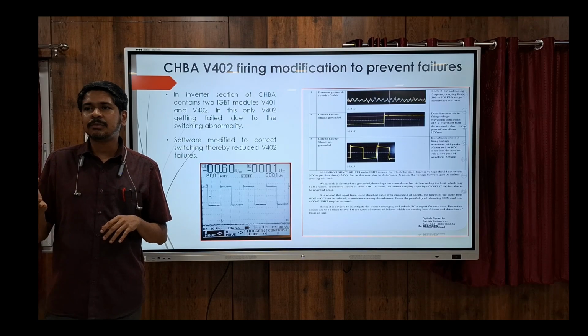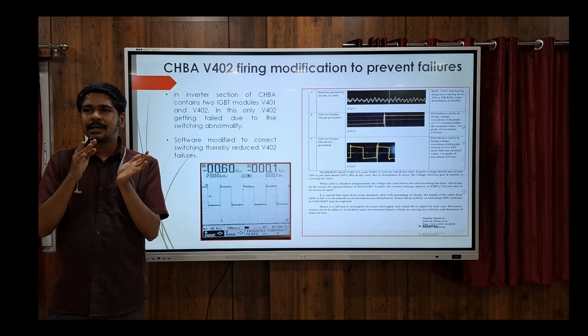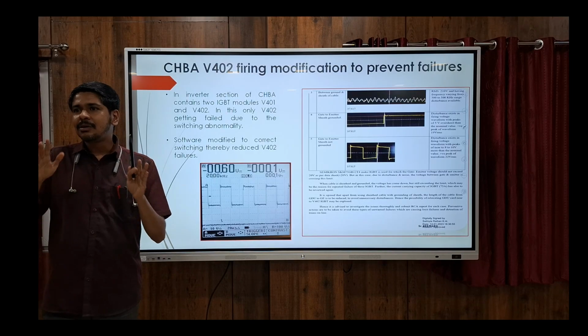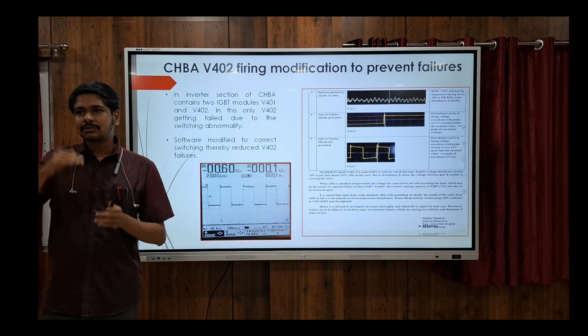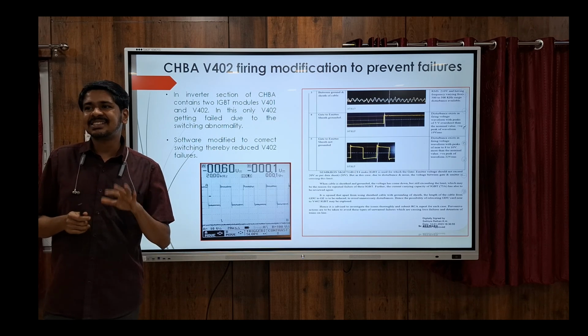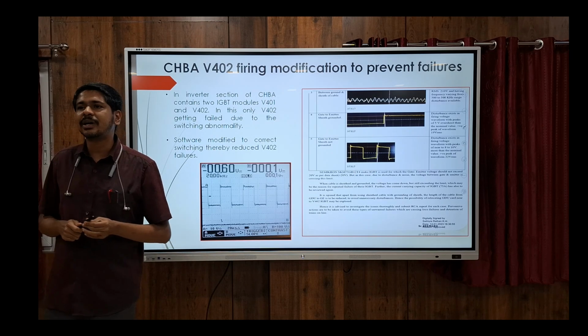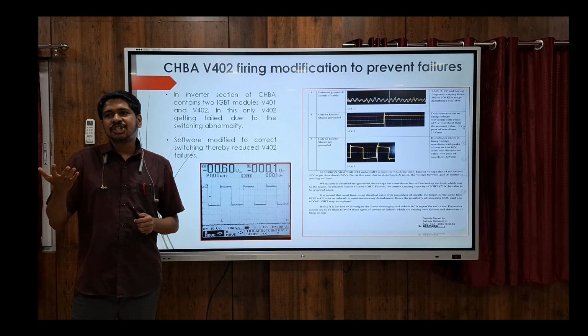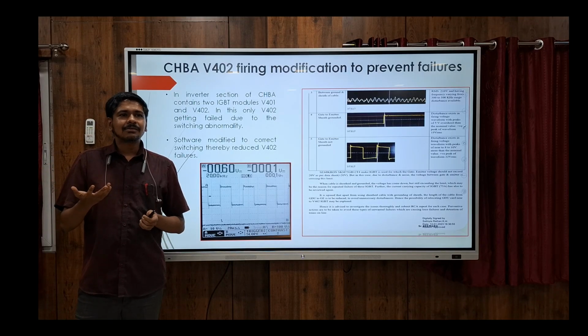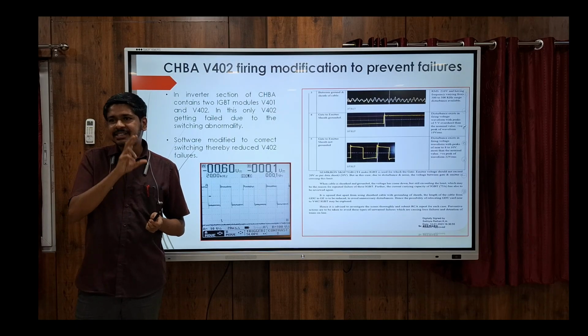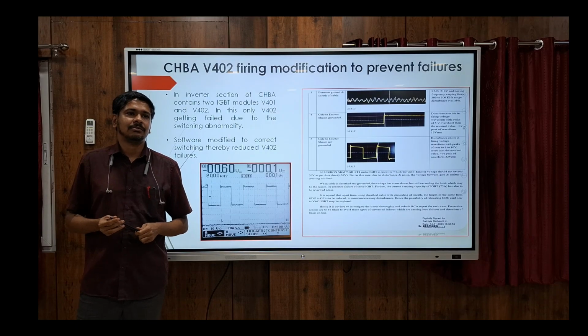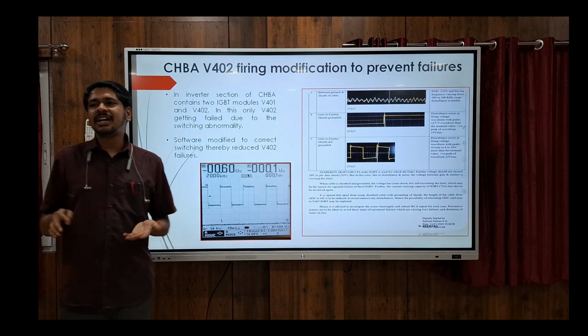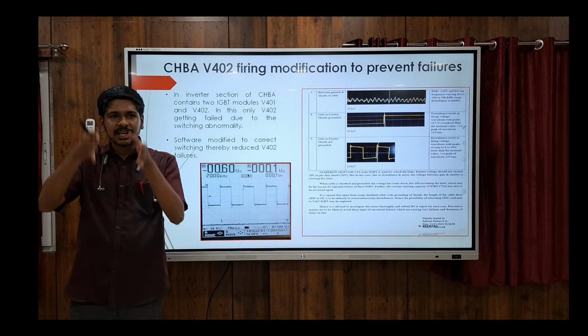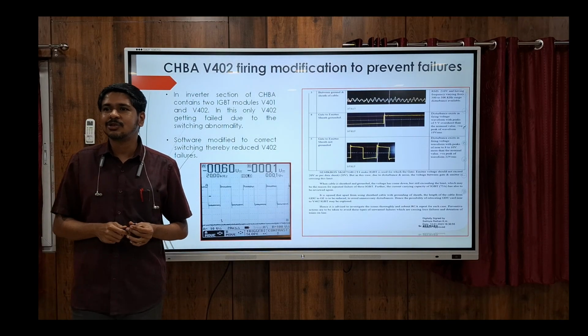So we advised ABB to equalize the firing cycle, and we have made it almost okay, and now failures have considerably reduced. For one cycle, the V402 IGBT, since it was subjected to heavy stress, failed a lot, so we have changed one cycle for that. Now the software has been adjusted so that the firing pattern is equalized and it is almost normal.